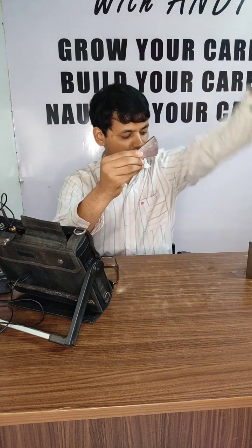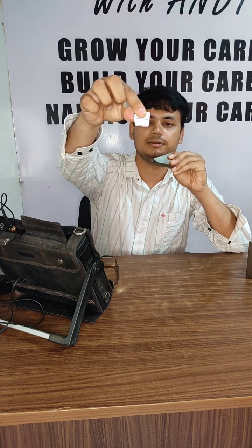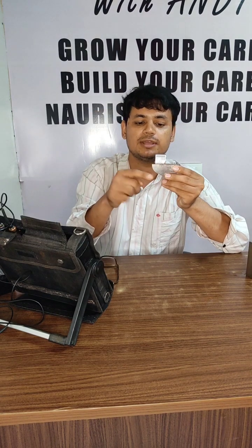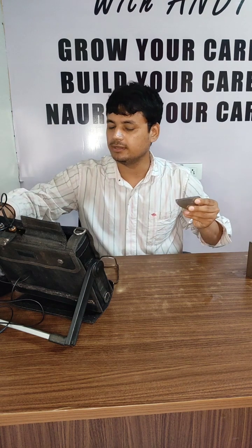So this is also a small block, called the IIW V2 block, International Institute of Welding V2 block. This is used for calibration of the angled probe. Okay, we have to put our probe like this, with the crystal facing downward, and here we have to set this middle one. You can see that there is a 10 written over here, and you have to put it like this, and then you see the beam path coming. From here to here, the beam path is 50 mm, and when you turn it to here, with the wire on the back, you have to see that this comes to 25. Okay, and then you complete the calibration.